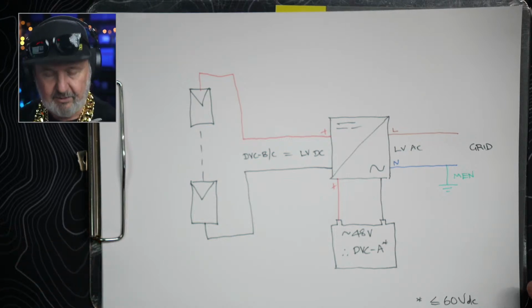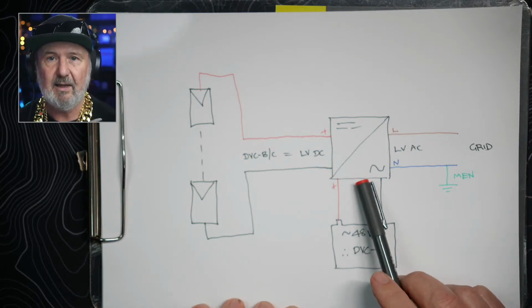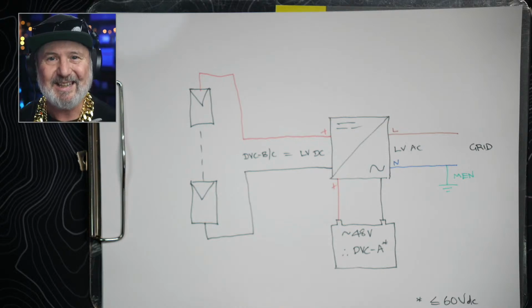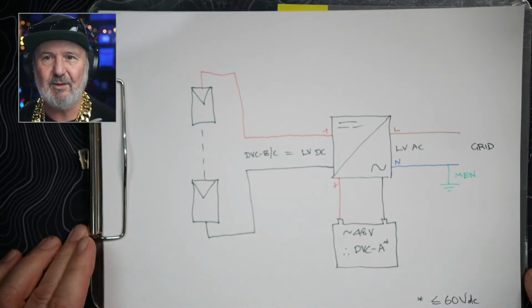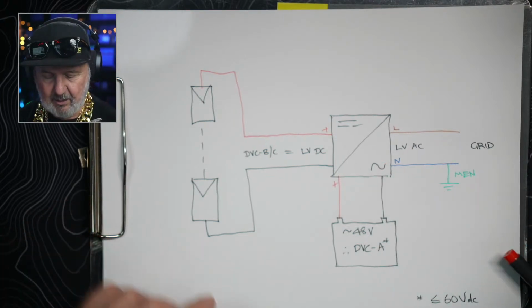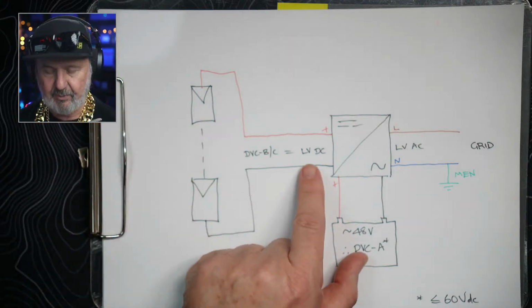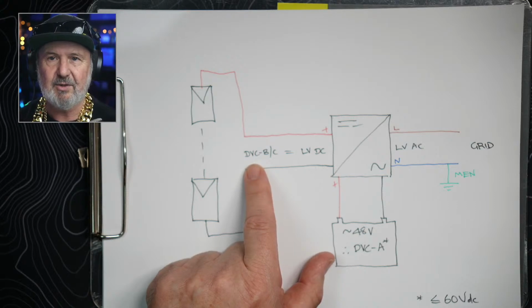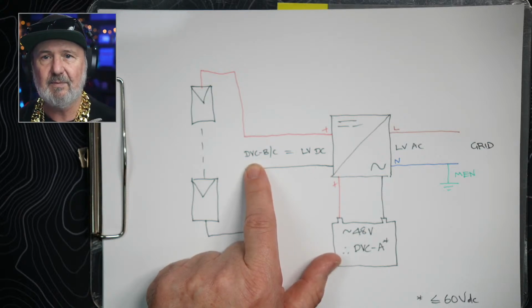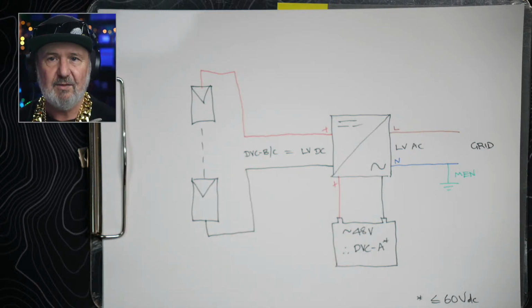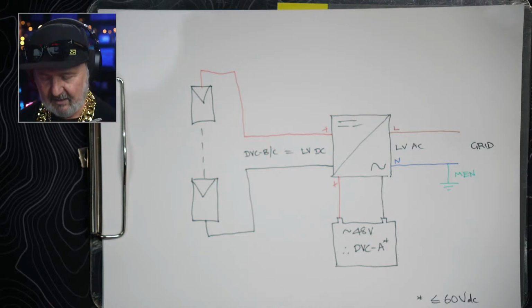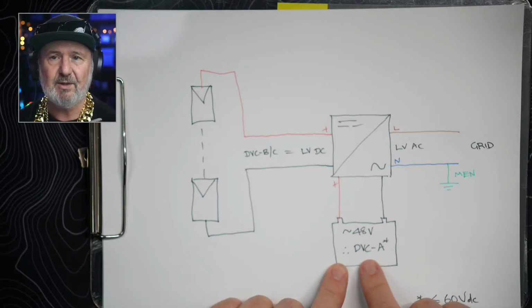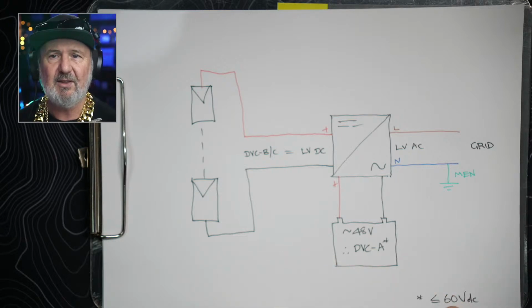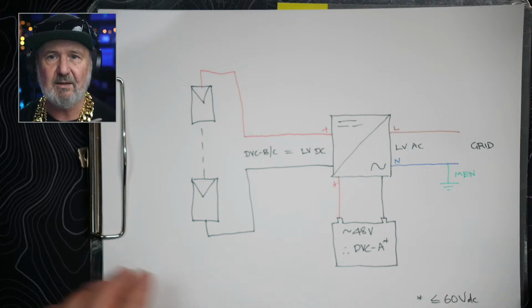Yeah, right. So let's look at this scenario where we've got an inverter. And of course, just to remind you, the standards now refer to PCE, power conversion equipment, not inverters or charge controllers generally. They'll use a generic term, PCE. So this is the PCE. We've got a PV array here, and this PV array is operating at LV, which can also be described using decisive voltage classifications. So it's DVC-B or C. B is 60 to 120 volts and C is above 120. But as far as the battery standard is concerned, B and C are equivalent to LV as defined in AS/NZS 3000. The battery system here is a nominal 48 volt battery, so it's categorized as DVC-A, which is anything less than or equal to 60 volts DC.